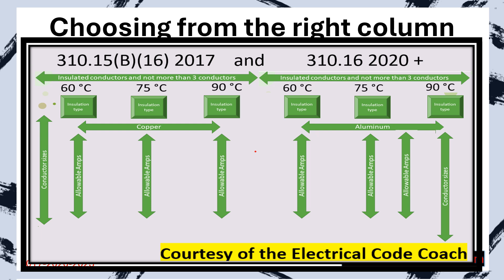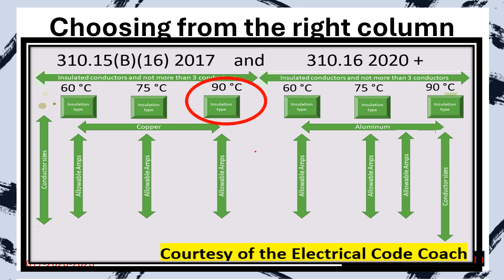Now let's talk about choosing from the right column — this is the last step before we start doing questions. Up until this point we've most often chosen from the 75°C column. There will be times we choose from 60°C, but now we start choosing from the 90°C column. 99% of the time you're going to choose from the 90°C column any time you're doing bundling adjustments or temperature corrections.